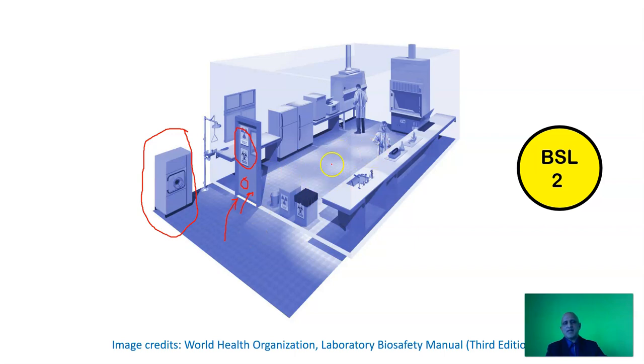The next aspect of this lab is the location of the biological safety cabinet and the fume hood. Both of these are located at the end of the facility. This ensures that all the air entering flows over the floor and the personnel prior to exiting via the HEPA filters. Both cabinets have to be hard ducted into the building and incorporated into the building design.